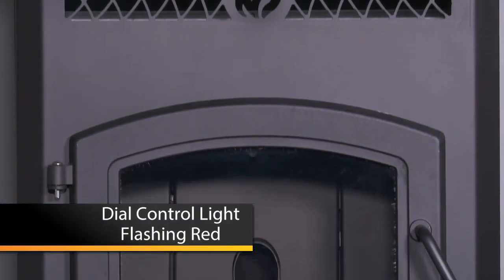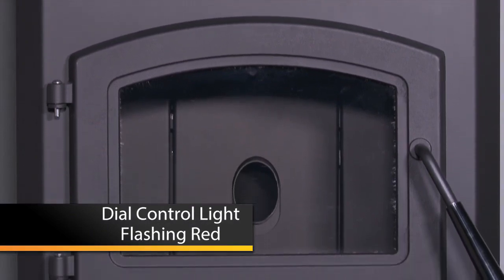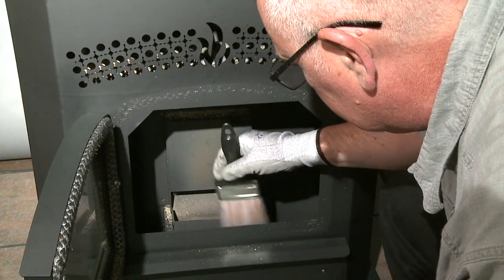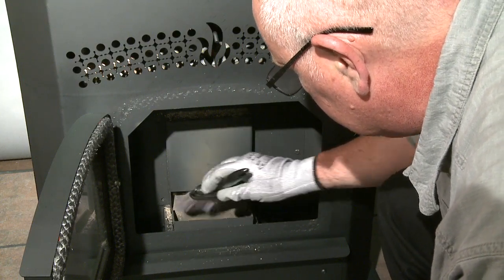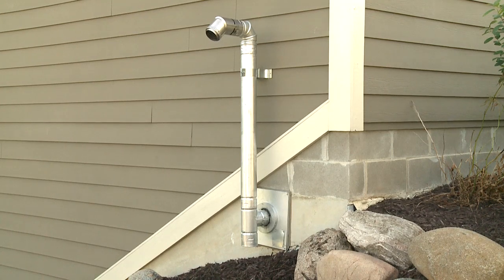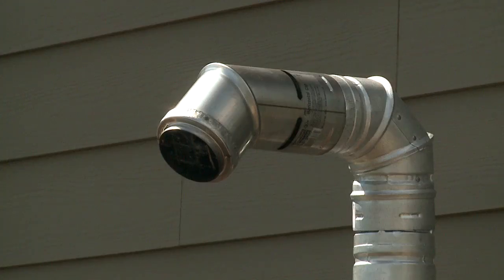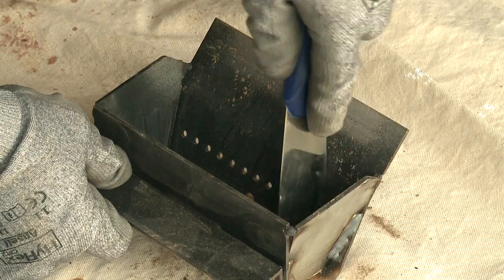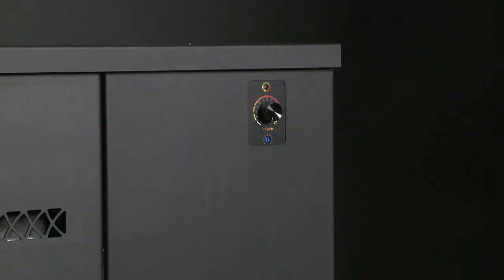Check to make sure the entire unit and exhaust venting system are clean. Heavy buildups in the burn pot or ash buildup in the unit or exhaust vent system can restrict airflow and cause the unit to shut off. Clean the unit and attempt to relight. Next, check the dial control. If the LED light is flashing red, pay attention to the number of flashes.